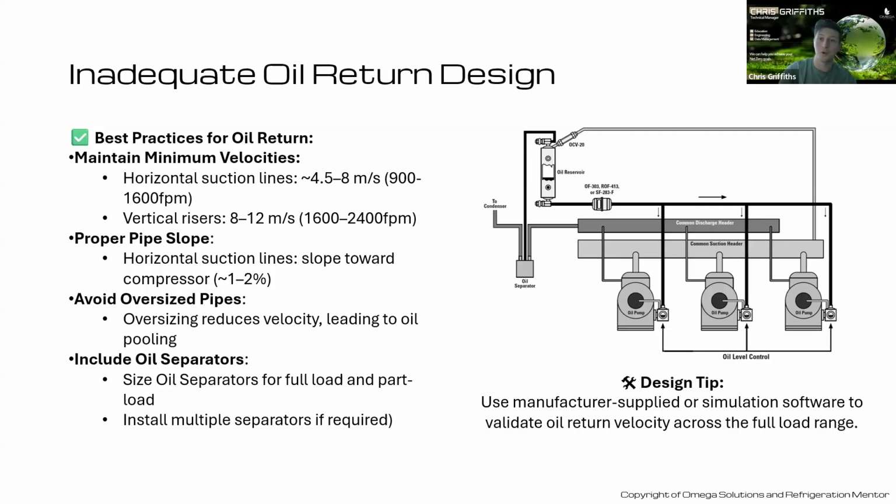Designers of equipment are doing their due diligence, but they can't design that equipment to suit every single scenario that's out there. So if you do find an odd site and you're scratching your head thinking, why isn't this working? At least if you know how to size an oil separator system, you can do your checks to see, is this the correct system for that application, for that site?